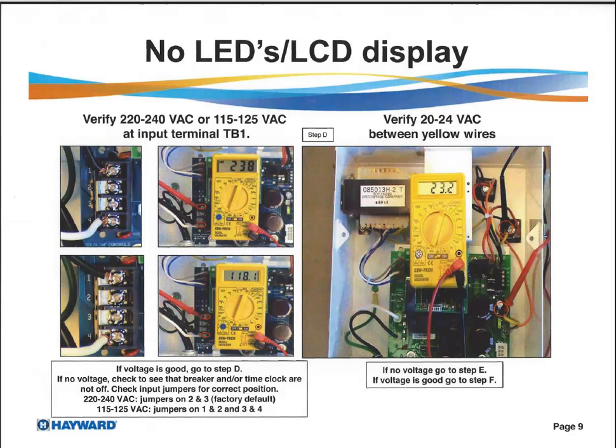This is troubleshooting 101. The big thing I see out there on a new install is you have no lights, or things come up very dimly and then shut down. Again, I would read and understand your manual, but it comes pre-wired for 240. 2 and 3 is jumped. That's 240, so you're using 1 and 4. Again, this could be an old book, so you need to read and understand your manual. If you have a 115 volt supply and you connect it there, you will not get voltage.